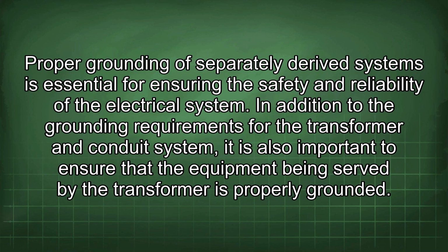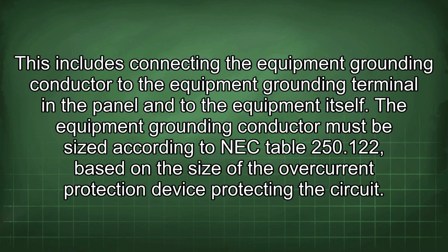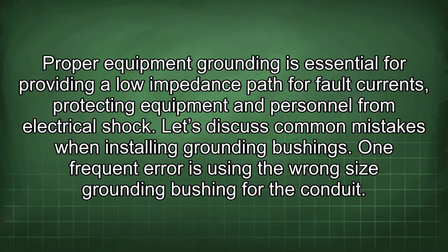In addition to the grounding requirements for the transformer and conduit system, it is also important to ensure that the equipment being served by the transformer is properly grounded. This includes connecting the equipment grounding conductor to the equipment grounding terminal in the panel and to the equipment itself. The equipment grounding conductor must be sized according to NEC Table 250.122, based on the size of the overcurrent protection device protecting the circuit. Proper equipment grounding is essential for providing a low impedance path for fault currents, protecting equipment and personnel from electrical shock.